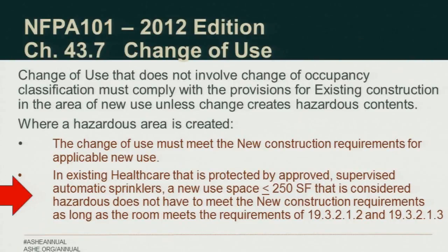No rating. So you've got that room that needs to be storage. It's sprinklered. You've got a self-closing door. It's less than 250 square feet. You can use this provision. It has to have positive latching.